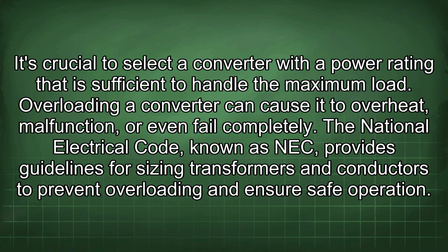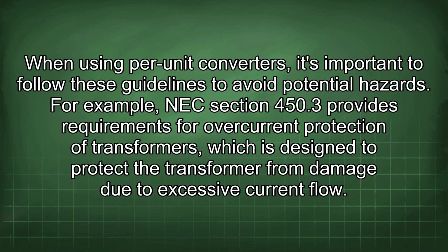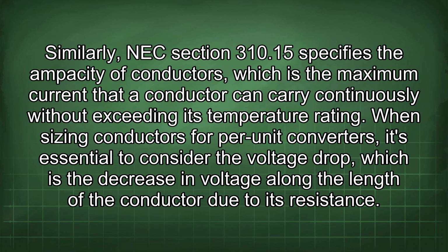The National Electrical Code, known as NEC, provides guidelines for sizing transformers and conductors to prevent overloading and ensure safe operation. When using per unit converters, it's important to follow these guidelines to avoid potential hazards. For example, NEC Section 450.3 provides requirements for overcurrent protection of transformers, which is designed to protect the transformer from damage due to excessive current flow. Similarly, NEC Section 310.15 specifies the ampacity of conductors, which is the maximum current that a conductor can carry continuously without exceeding its temperature rating.